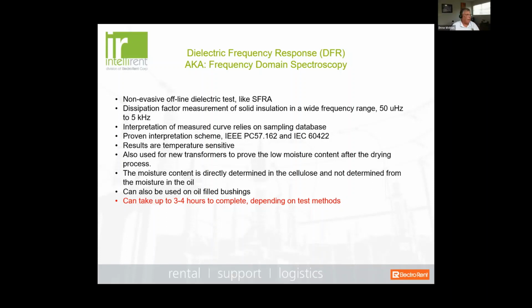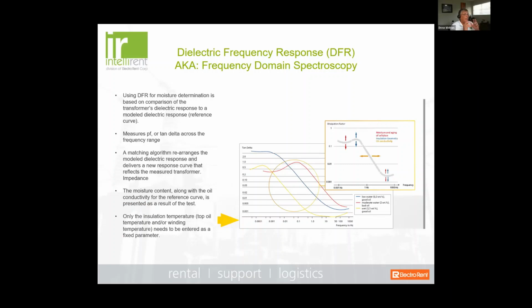Now, how was this developed? Well, I think it first became an IEEE standard back in 1997, C57.162. And it is temperature sensitive, so it's important to know what the temperature of the transformer is when you're doing the test, and it can take a while to test. But basically, it was developed under laboratory standards where they did a Karl Fischer titration on paper insulation, and based on the tangent delta measurement that they took, knowing what the exact moisture content was, they looked at the geometry of the response.